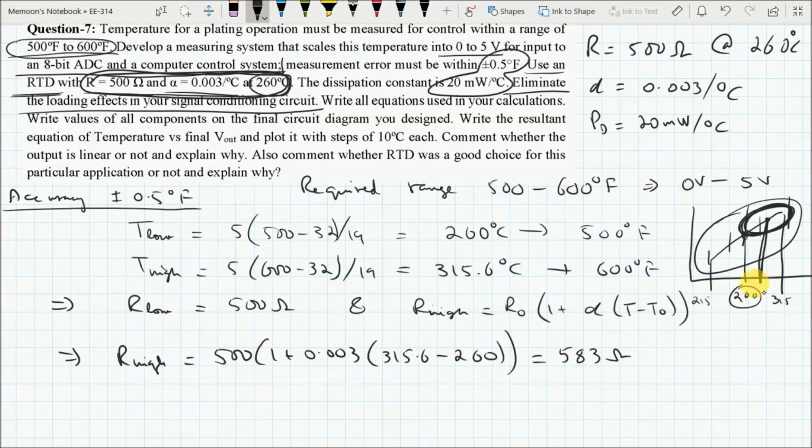But it will not be completely wrong to use a larger range if linear approximation can still be applied within that range, and from 215 to 315, within 100 degrees Celsius, the behavior of RTDs is fairly close to linear. So that is not a bad approximation.